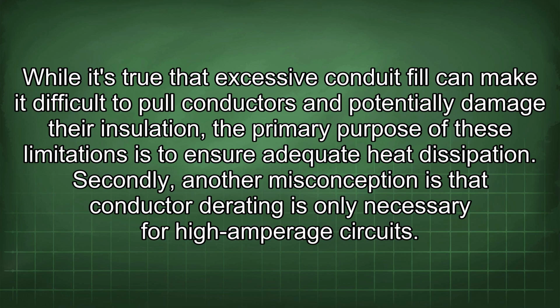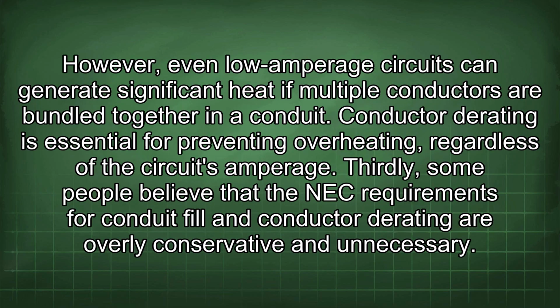Secondly, another misconception is that conductor derating is only necessary for high amperage circuits. However, even low amperage circuits can generate significant heat if multiple conductors are bundled together in a conduit. Conductor derating is essential for preventing overheating regardless of the circuit's amperage.